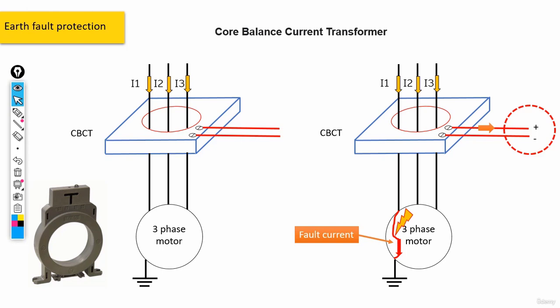The first device that we can use would be the core balanced current transformer. We've actually seen its abbreviation before, CBCT. Now, when we want to connect our three-phase system to our motor, the electrical currents should actually move through our CBCT transformer. And by the way, a CBCT transformer has a shape like this. Now, what is the duty of this equipment? We said that we would have a current coming from these phases, I1, 2, and 3.